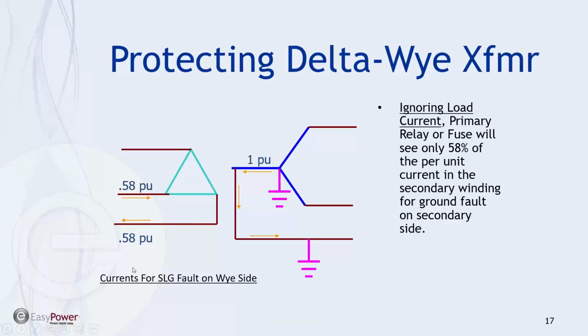And again, this is only for primary monitoring and a single line to ground fault on the Y side. But what this results in is we only see the fuse in the primary side will only see 58% per unit of the current in the secondary winding. So in our protection scheme, we need to account for this offset in the damage curve.